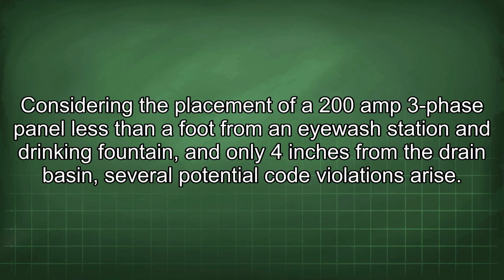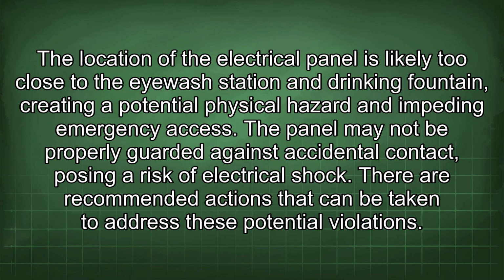Considering the placement of a 200 amp 3-phase panel less than a foot from an eyewash station and drinking fountain, and only 4 inches from the drain basin, several potential code violations arise. The location of the electrical panel is likely too close to the eyewash station and drinking fountain, creating a potential physical hazard and impeding emergency access. The panel may not be properly guarded against accidental contact, posing a risk of electrical shock.